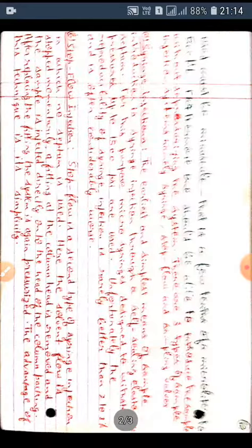Sample injection system is most often the limiting factor in the precision of liquid chromatography measurement. The importance lies in the reproducibility with which samples can be introduced onto the column packing. The problem is enhanced by band broadening, which accompanies overloading columns. Thus, the volumes used must be minuscule, that is, a few tenths of a microliter to 500 microliters. Furthermore, one should be able to introduce the sample without depressurizing the system.